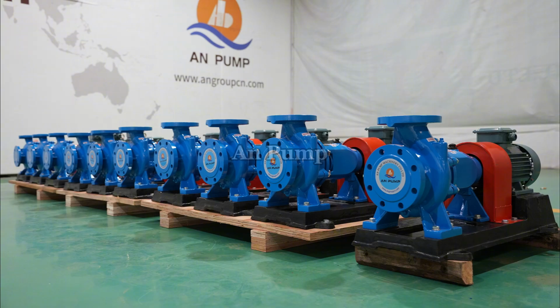Here are 5 key criteria. First, your hydraulic duty point. That means the flow rate and total head you need. You want to match the pump's best efficiency point to save energy and reduce mechanical stress. Second, fluid properties. Temperature, viscosity, vapor pressure, pH, specific gravity, and solids content all affect material selection, impeller type, and seal design. Third, net positive suction head available, or NPSH. This tells you whether the pump will cavitate.